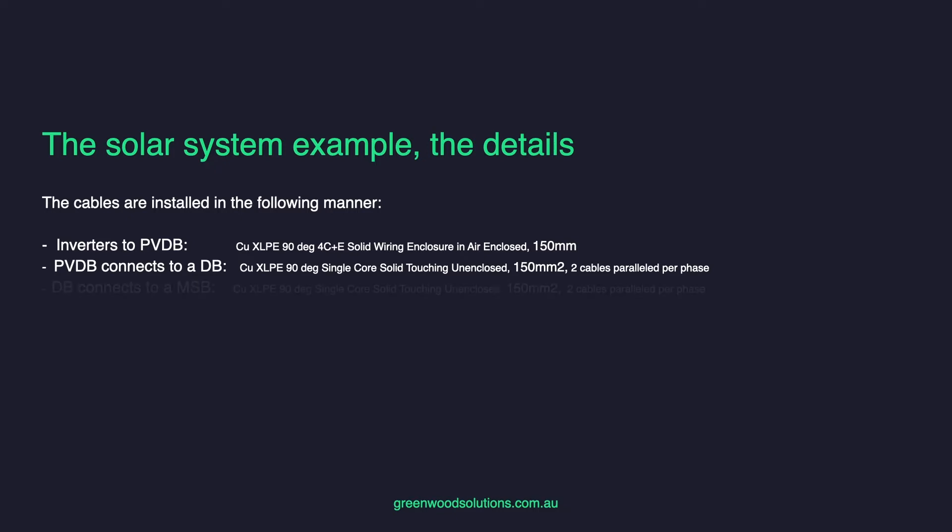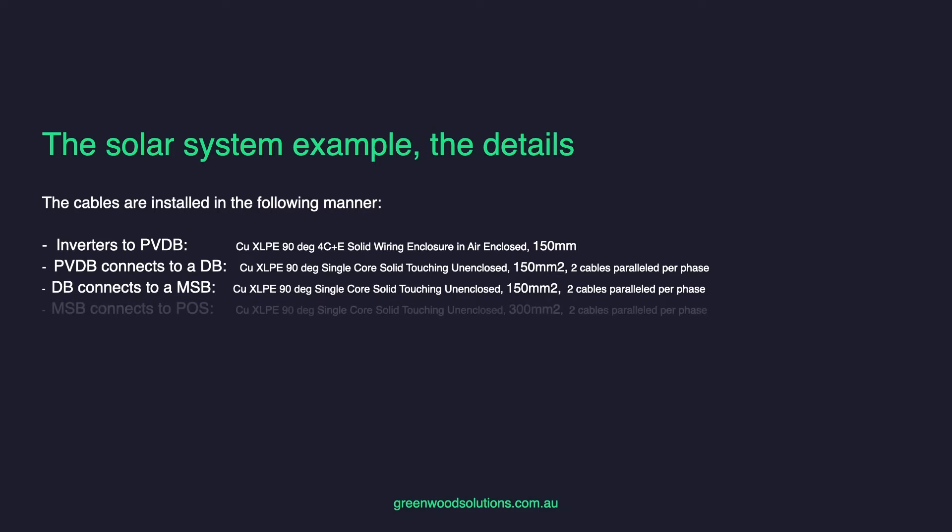The DB connects to the MSB using copper, XLPE, 90 degree, single core, solid, touching, unenclosed, 150mm squared, two cables paralleled per phase. The MSB connects to the point of supply using copper, XLPE, 90 degree, single core, solid, touching, unenclosed, 300mm squared cable, with two cables paralleled per phase.